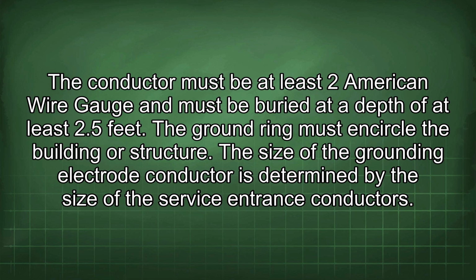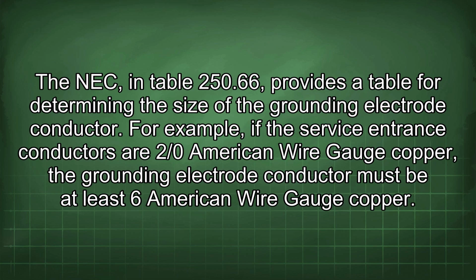The size of the grounding electrode conductor is determined by the size of the service entrance conductors. The NEC, in Table 250.66, provides a table for determining the size of the grounding electrode conductor. For example, if the service entrance conductors are 2/0 American wire gauge copper, the grounding electrode conductor must be at least 6 American wire gauge copper.